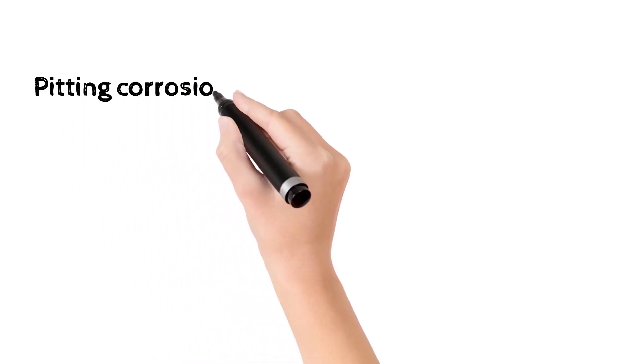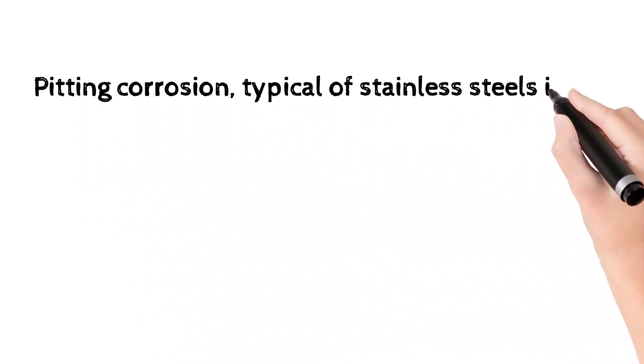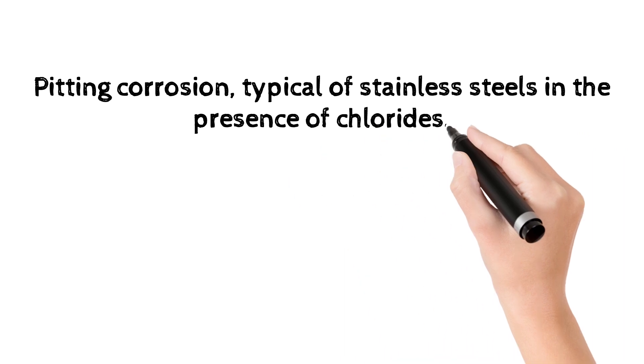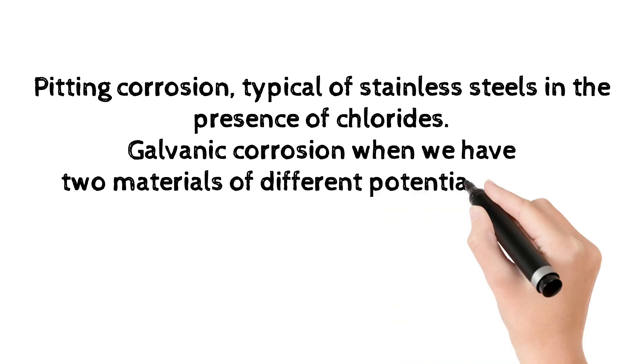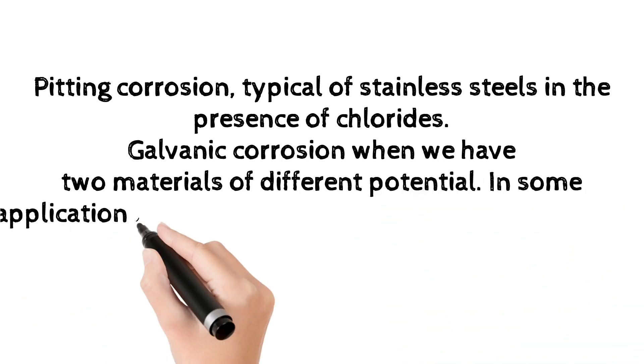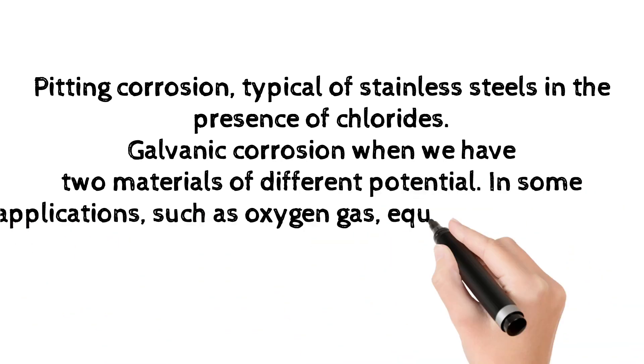Pitting corrosion, typical of stainless steels in the presence of chlorides. Galvanic corrosion when we have two materials of different potential. In some applications, such as oxygen gas, equipotential bonding is used.